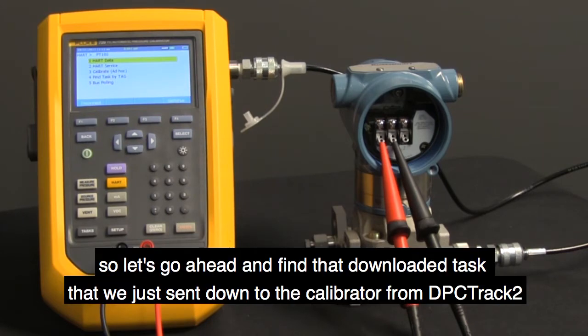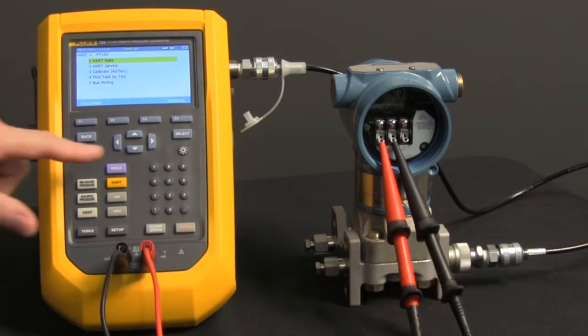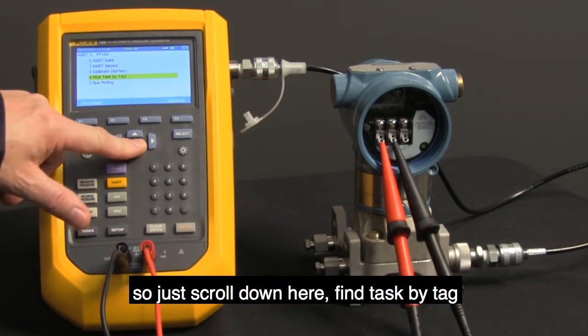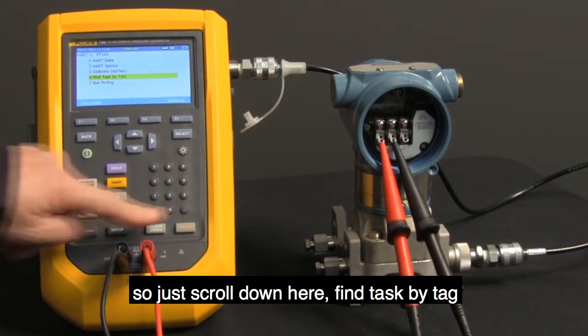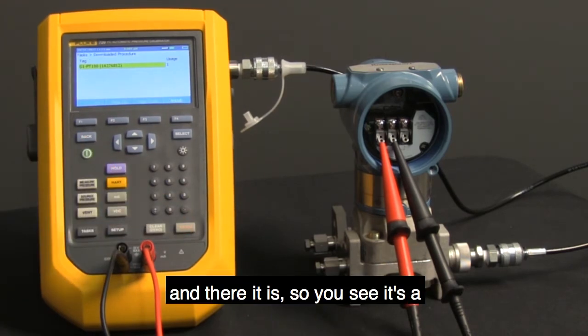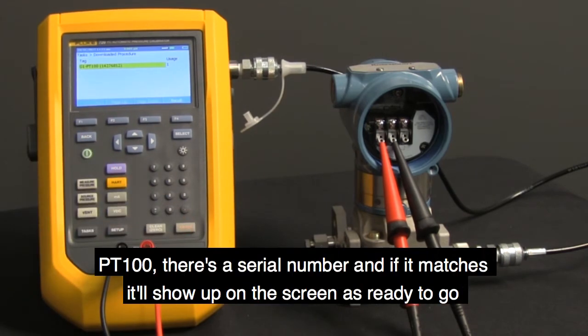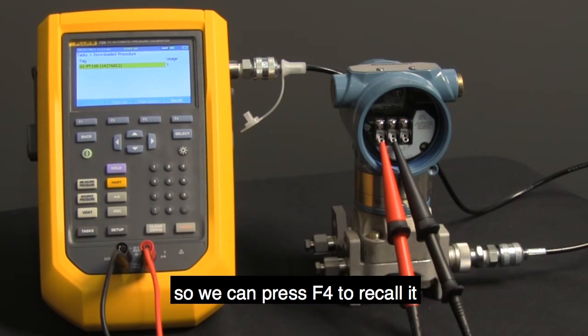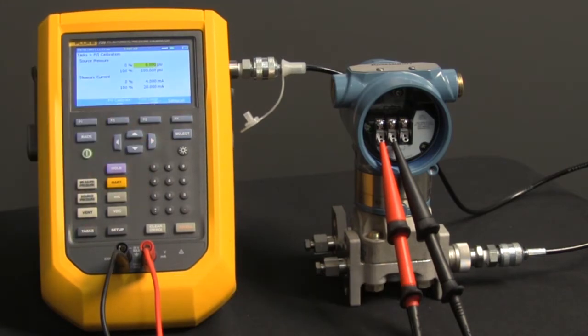So let's go ahead and find that downloaded task that we just sent down to the calibrator from DPC Track 2. So we'll just scroll down here, find task by tag, and there it is. So you see it's a PT100, there's a serial number, and if it matches up, it'll show up on the screen as ready to go. So we can press F4 to recall it.